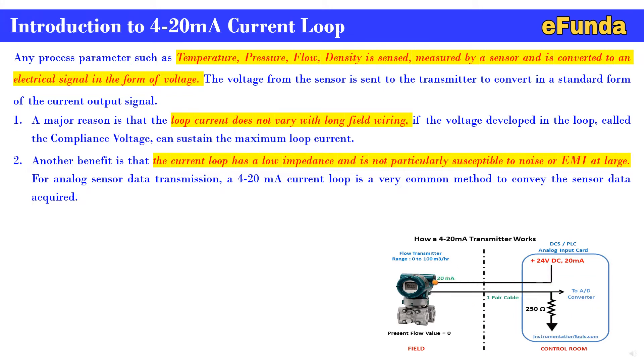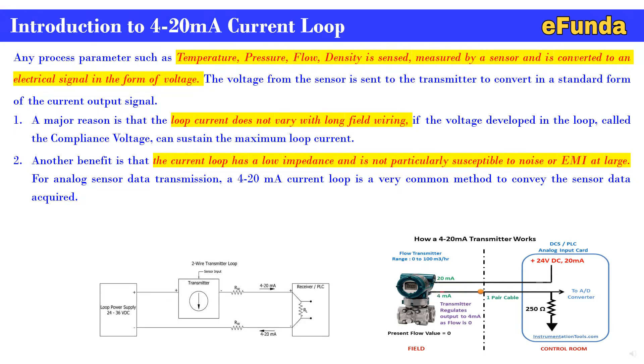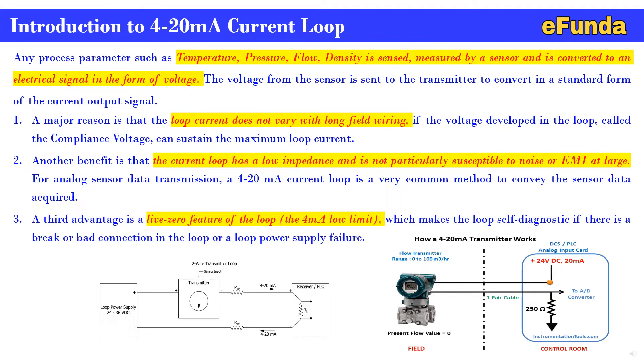For analog sensor data transmission, the 4 to 20 milliamp current loop is a very common method to convey sensor data. One can refer to the two-wire loop transmitter where the power supply is connected to the transmitter and through a resistor is received at the PLC card or system side. A third advantage is the live zero feature — the 4 milliamp low limit makes the loop self-diagnostic in case of a break, bad connection, or power supply failure.